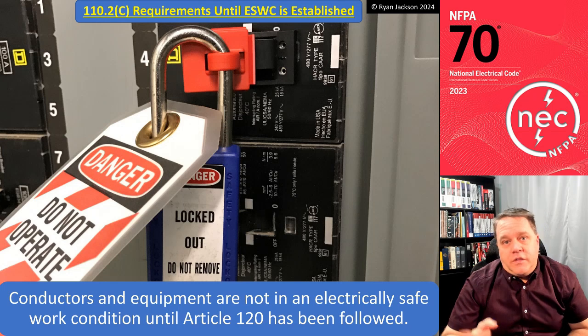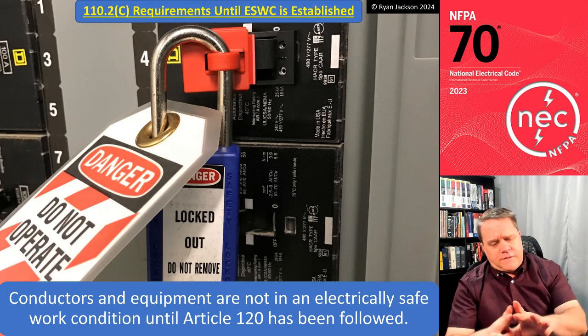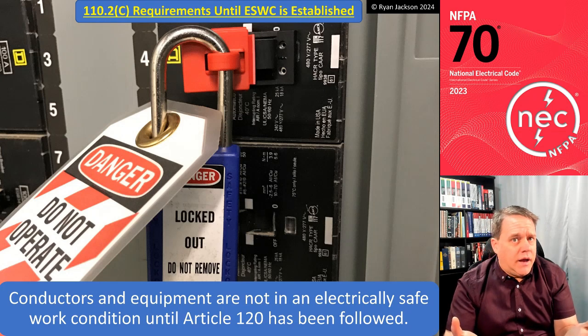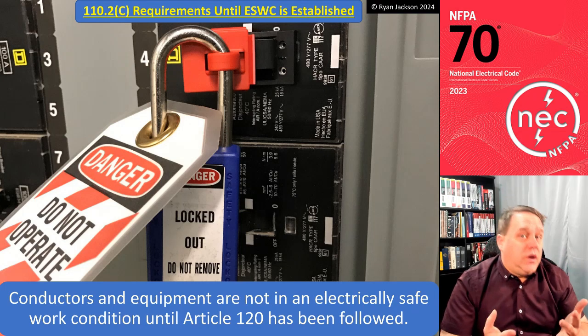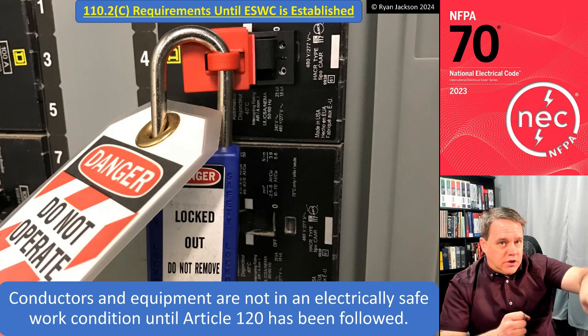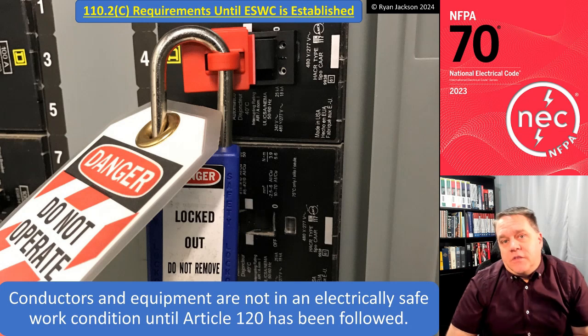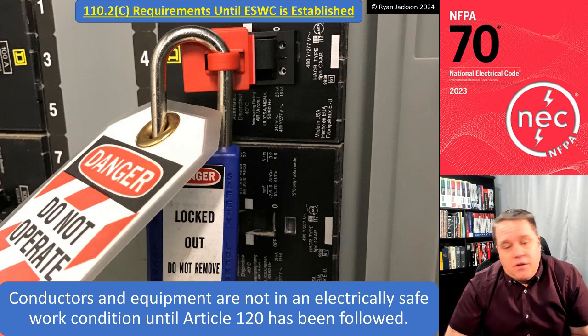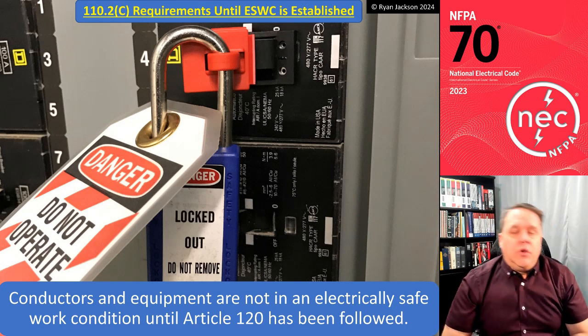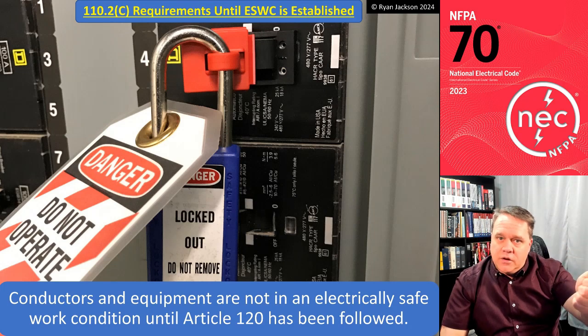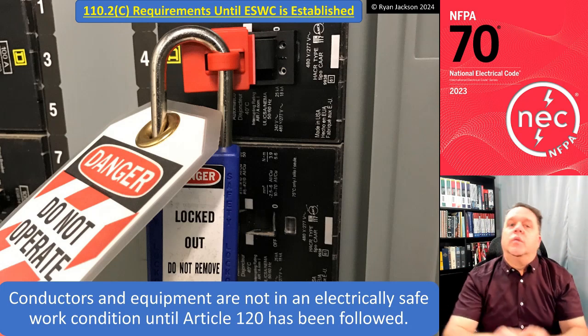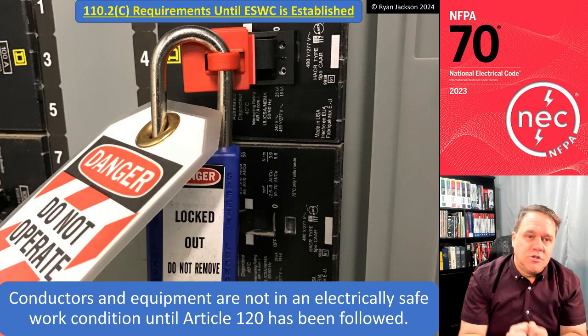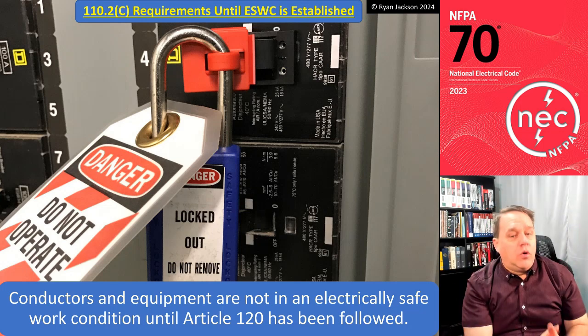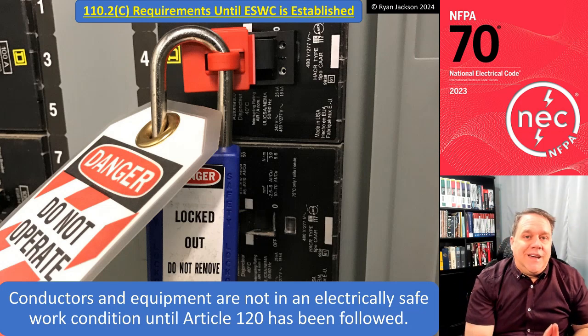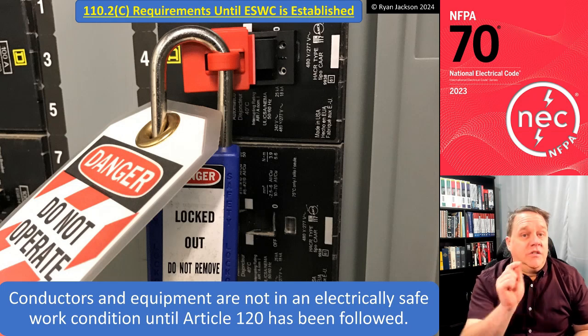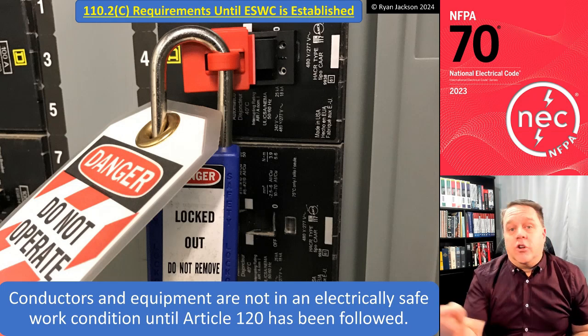So one of the things that we have to do is we have to figure out all sources of electric supply. Once we've figured out what we need to shut off and we go ahead and shut it off, does that mean that we're in an electrically safe work condition? No, absolutely not. We need to lock it out or put a tagout device on it. We need to put our tag on it. We need to verify the absence of voltage. Only after you've gone through the whole thing are you in an electrically safe work condition. So until you've done it, it's considered on.